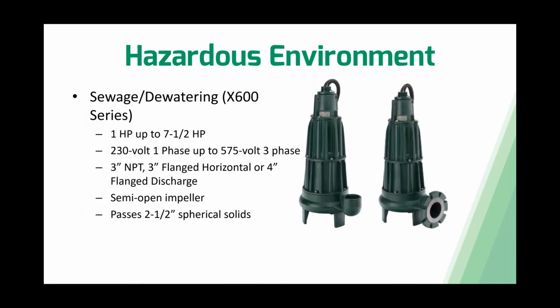The next offering within the sewage and dewatering is our X600 series. These, like the X400s, are the more commercialized version. We offer 1 horsepower, which is the 611, up to the 661, which is our 7.5 horsepower. The voltage and phase here within this category of pumps is 230 volt single phase up to the 575 volt 3 phase, just like the X400 series. In the X600 series, though, you have a few different options of discharge capabilities. So as you can see here on the left, you can get the 3-inch NPT discharge for national pipe thread, or we offer it in 3-inch flanged or 4-inch flanged discharge. The impeller here, up to this point, we've heard vortex impeller. This X600 series has a semi-open impeller.